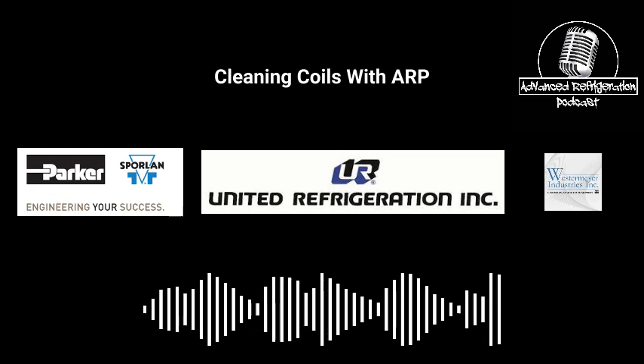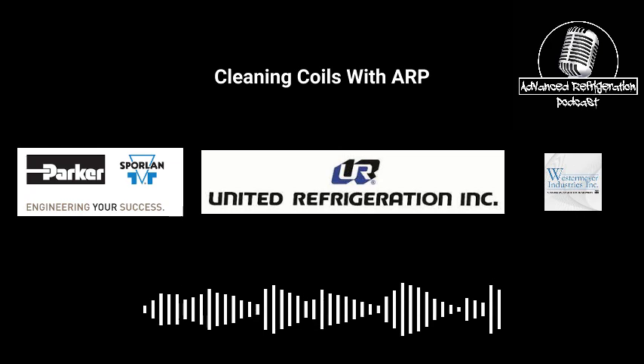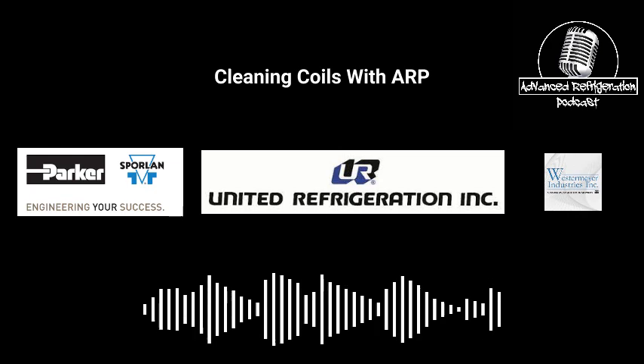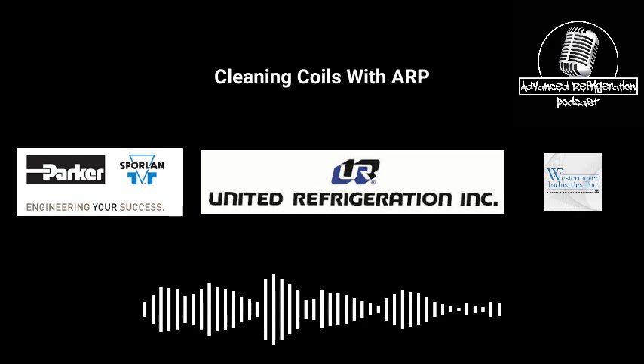But whatever, that's 2 hours that somebody else isn't going to have to do at 2 o'clock in the morning. And it's saving them energy. If those things are running with the condensers plugged, you're almost at the VFD limits. You're using more power on the VFDs, using more power on the racks. So everybody wins at that point. Their energy bill is going to drop. You keep the condensers clean, and their service calls are going to drop too.